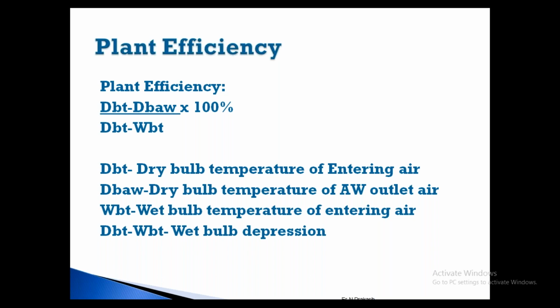If it is a 42-degree dry bulb and a wet bulb of 24, after the air washer we should try to get close to the wet bulb, that is, close to 24. If not 24, you should get 25 or 26. So it is the dry bulb entering minus the dry bulb leaving, divided by the dry bulb minus the wet bulb. It goes by the adiabatic saturation process, so the wet bulb will be the same.